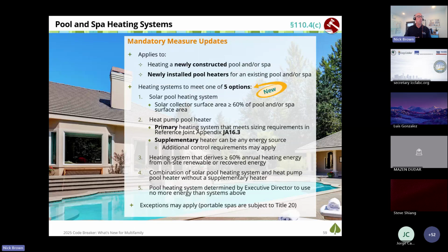Third option, you hire a mechanical engineer to show that your heating system derives at least 60% of the annual energy from on-site renewable or recovered sources. Option 4, combination solar thermal and heat pump without a supplementary heater. And an option 5 is reserved for other options that the CEC's executive director may determine is equivalent. So that's a pretty big deal.